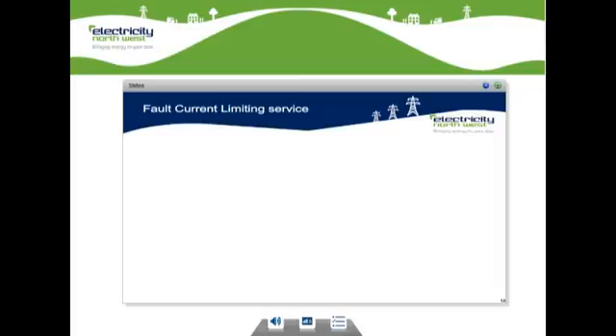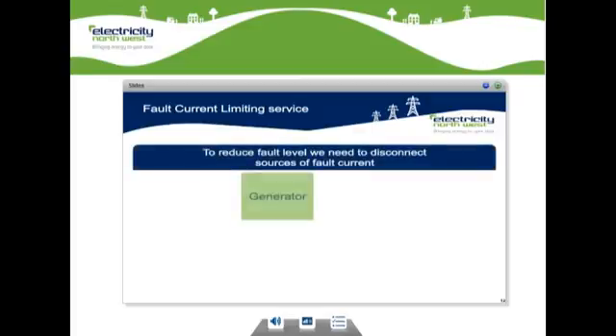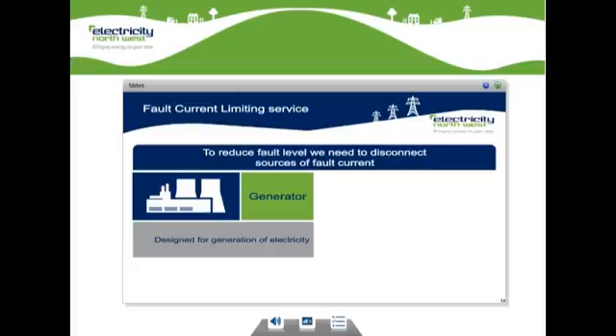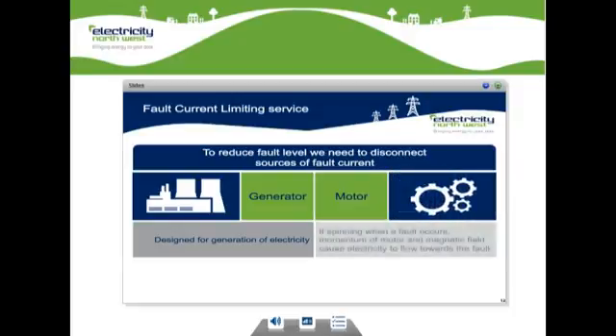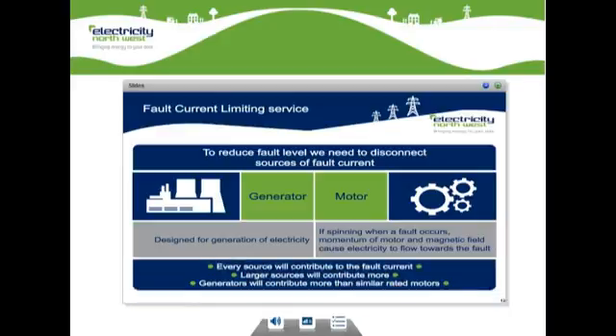The third technique we're going to trial is the fault current limiting service. Now, fault current can be generated from a number of sources, including customers' equipment running in synchronization with our network. The largest of these, rotating plant, are either designed to generate electricity or can be large synchronous motors that usually consume electricity but can flip into becoming a generator when the supply voltage drops. These rotating machines can supply up to 8 times their load current at the time of fault as a fault current.